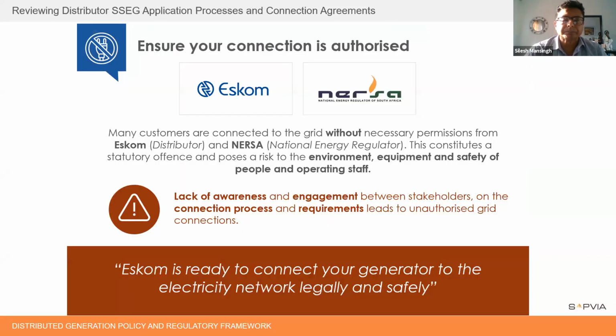Before you connect your generator to the grid, you need to make sure, whether it's Eskom, the local municipality, or whoever supplies you, that you have the respective permission. And from NERSA, in terms of licensing, or now possibly just registration for those generators as required and enforced by NERSA, we need to make sure the necessary permissions are granted before you connect.